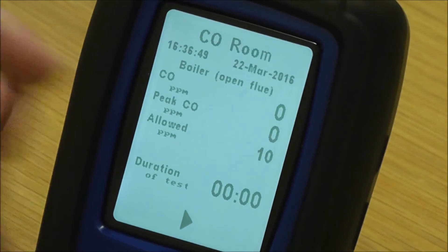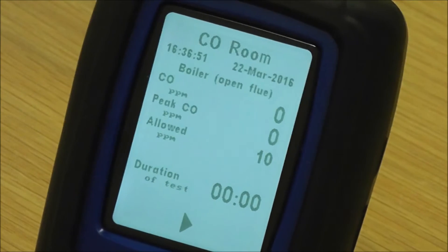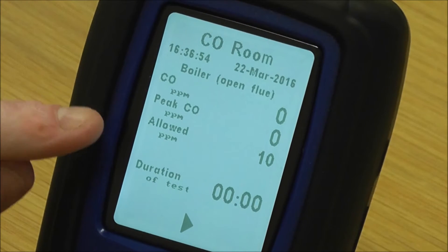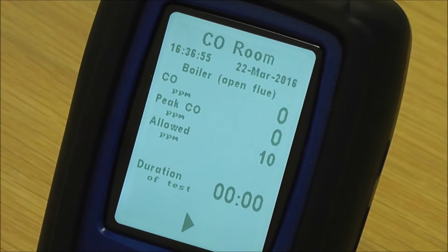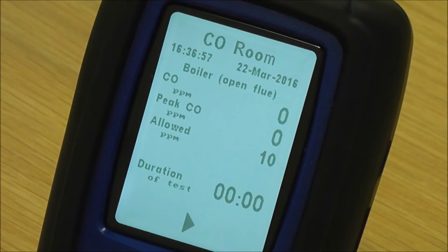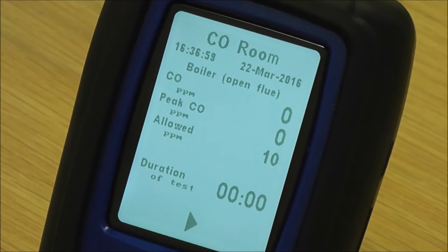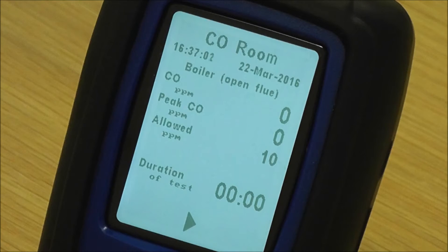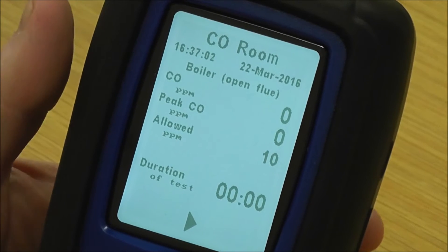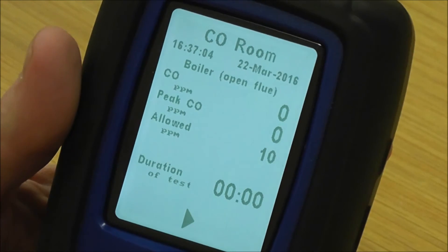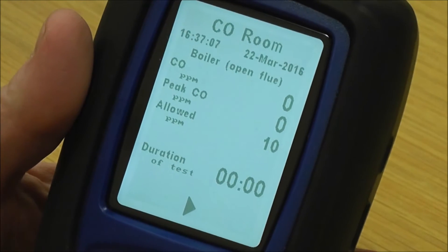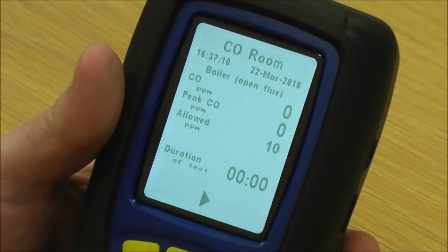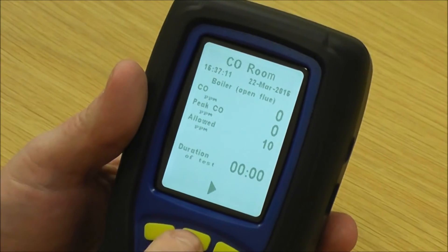What you see on the page here is the CO ppm, which is the actual reading of CO currently. Then you've got a peak CO, which is the highest level of CO seen so far during the test. And then the allowance on this particular appliance is 10 ppm, and then you have the duration at the bottom. Once this is set up with your flue probe and tripod, you start the test.